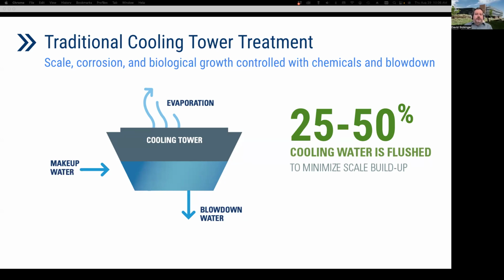The quantity of water evaporated is fixed. Approximately 1.8 gallons of water is evaporated for every ton-hour of cooling. So we're targeting savings from a reduction in water in the system blowdown. If you're not as familiar with cooling towers, the GSA website for this guide has an additional resources section with a link to a nice reference fact sheet titled Understanding Cooling Towers and How to Improve Water Efficiency. So next slide, please.